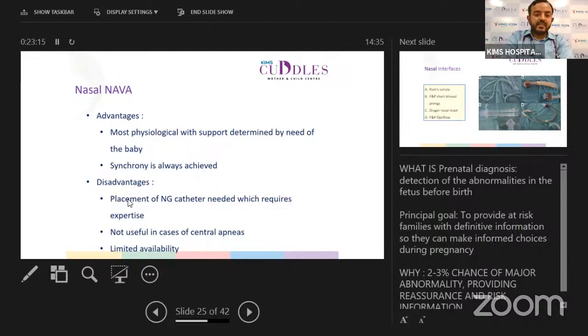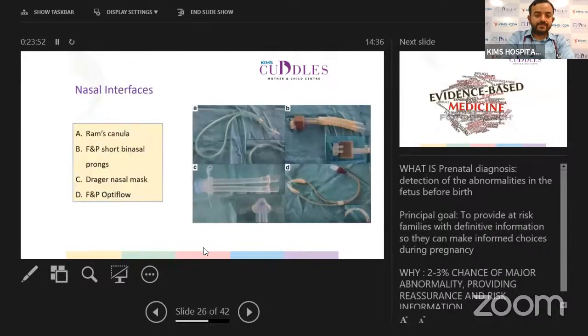The disadvantages: placement of a catheter. For detection of electrical activity of the diaphragm, catheters are inserted into the esophagus, and they should be fixed at the level of insertion of the diaphragmatic crura. This requires expertise and experience, and there is frequent dislodgement of the catheter. It is not used in central apnea, as the primary principle of NAVA is the electrical activity that is to be generated in the diaphragm. In babies with central apneas in which there is no respiratory drive, NAVA fails to provide respiratory support, and the problem is the limited availability.